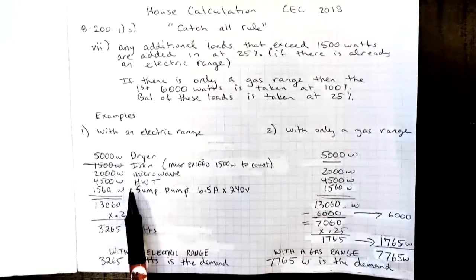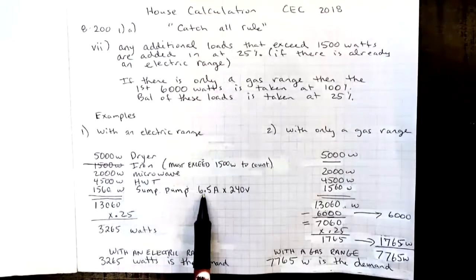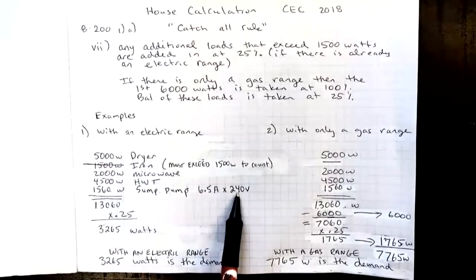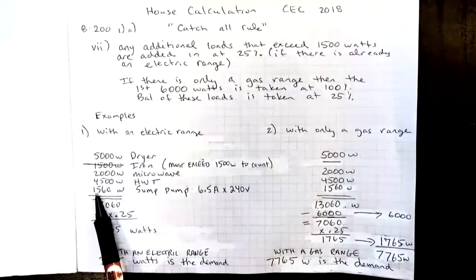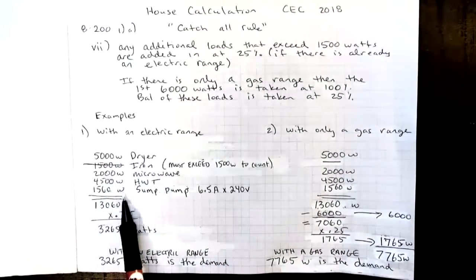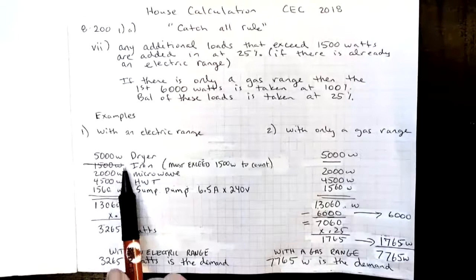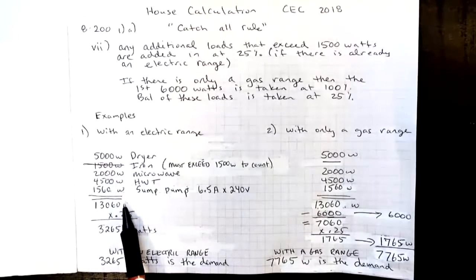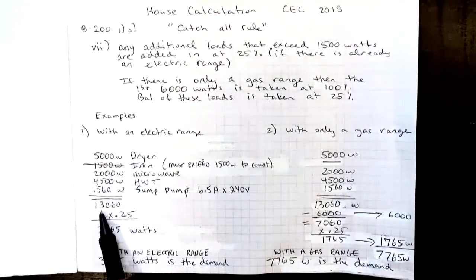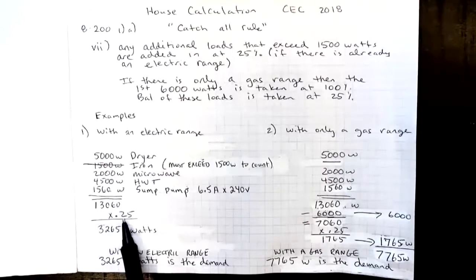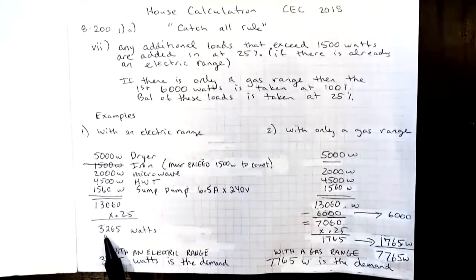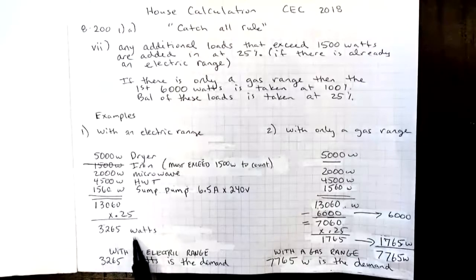Microwave, hot water tank, and then the sump pump, it's a 6.5 amp 240 volt sump pump, and that will add up to 1560 watts. So we will include that. Add up all of those items, it gives us 13,060, and we multiply that by 25% or 0.25, so the total demand that would go towards the service will be 3,265 watts.